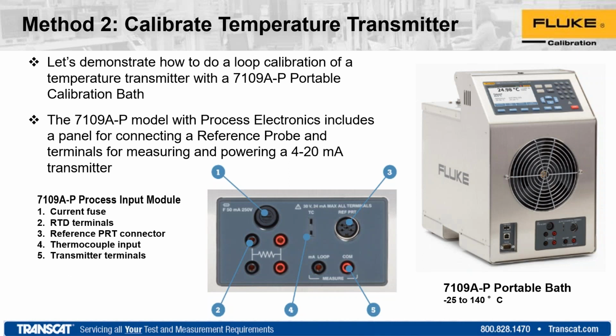So we're going to show you a demonstration here of an option that, if you go with the 7109A-P model, which is called a process option, builds in some additional features to the unit. So in the first example, we showed the bath had its own capability to run some programming. Now with this additional feature, you also have the option to run in a reference probe, as well as here you can see the milliamp loop. So you can actually source to the transmitter and get a reading as well.